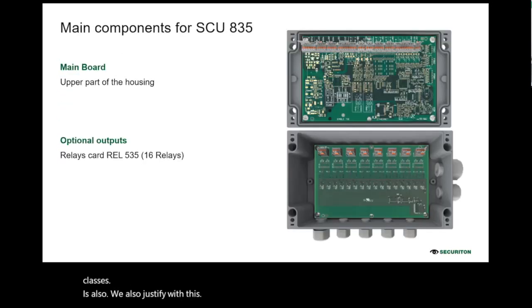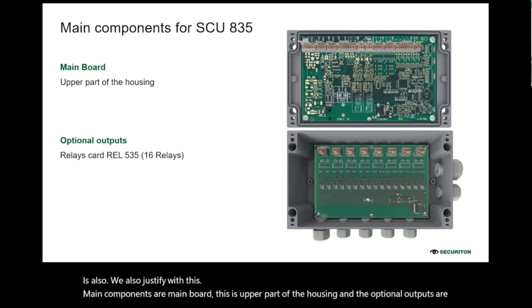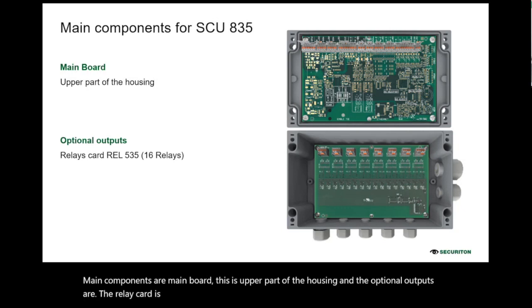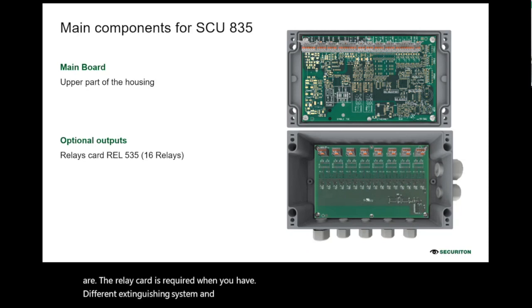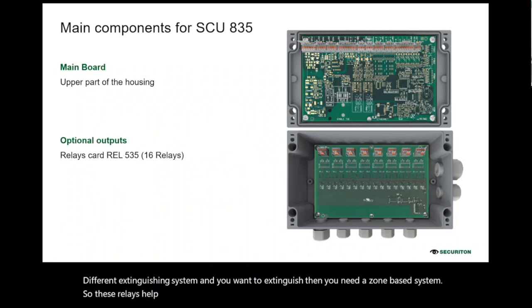The main components are the main board and the upper part of the housing. The optional outputs, the relay card, are required when you have different extinguishing systems and you want a zone-based system. So these relays help you in planning the zone-wise separation.